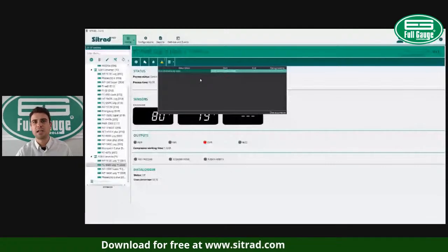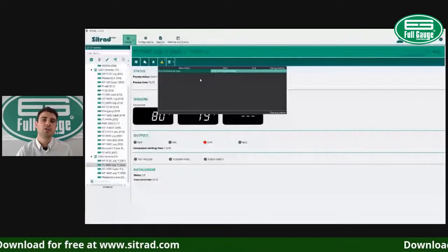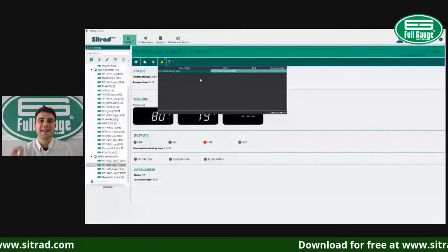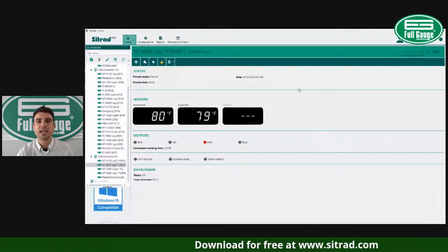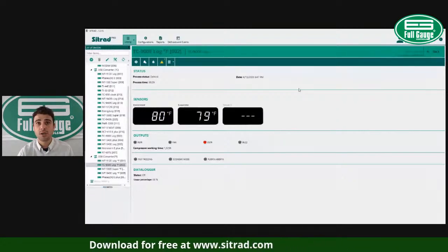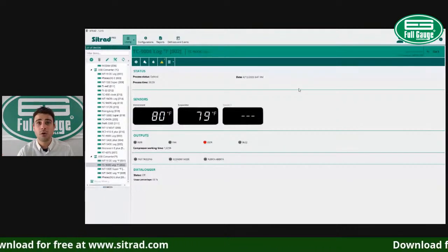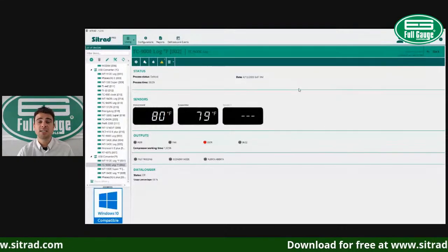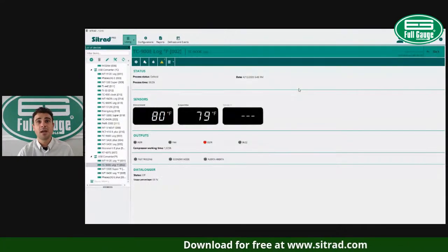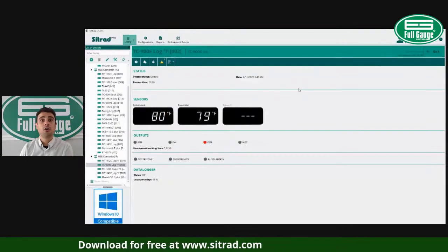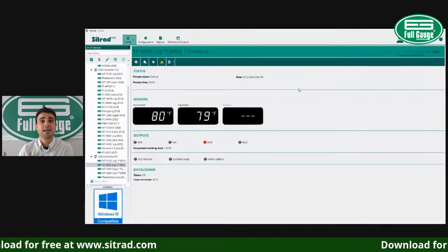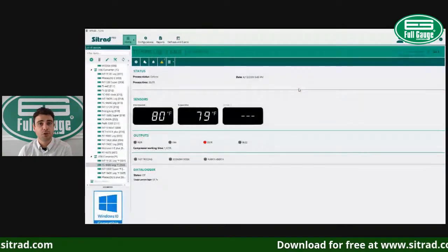Why do we have that alarm? Because on the freezer controller, you ideally want to terminate defrost based on temperature for an optimum defrost cycle. If your defrost cycle terminated by time, it was because your coil temperature could not reach the defrost termination temperature.